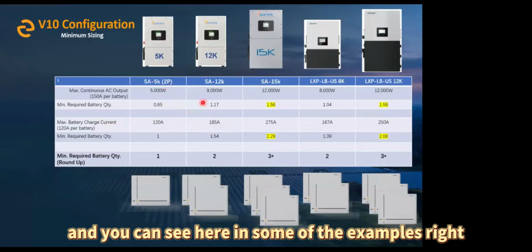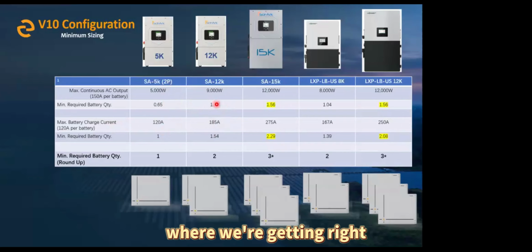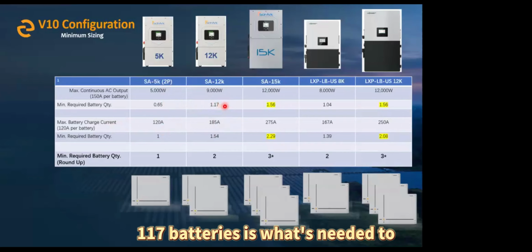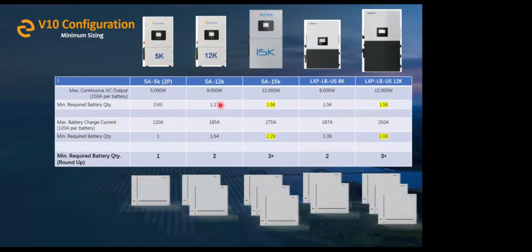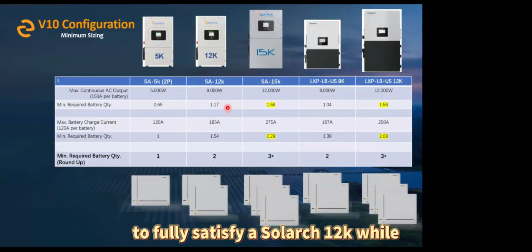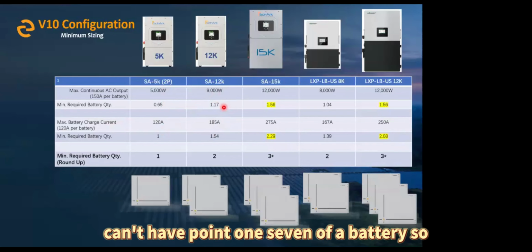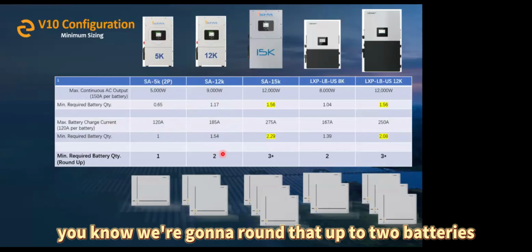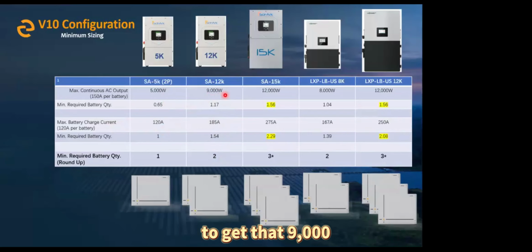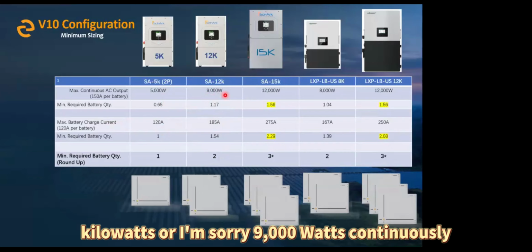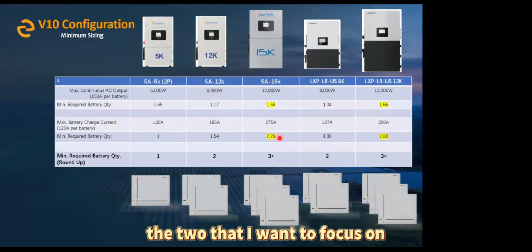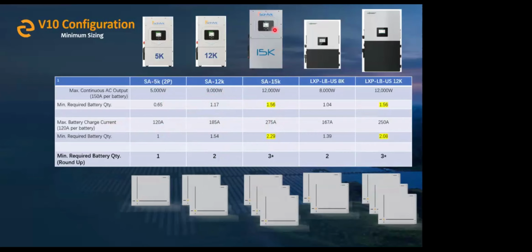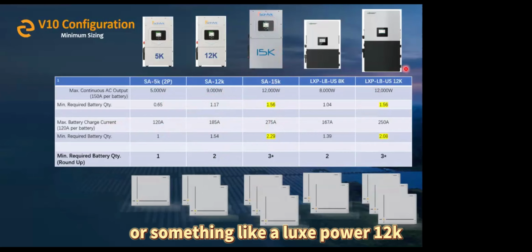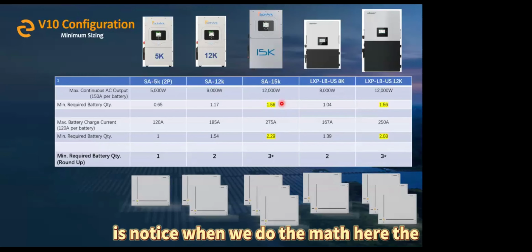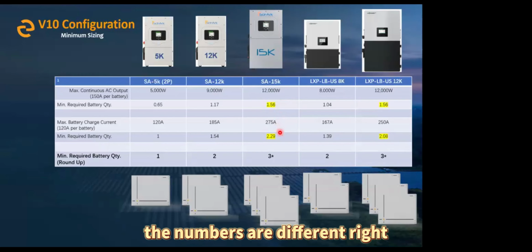And you can see here in some of the examples, we're getting 1.17 batteries is what's needed to fully satisfy a Sol-Ark 12K. Well, can't have 0.17 of a battery, so we're going to round that up to 2 batteries to get that 9,000 watts continuously. The 2 that I want to focus on, in the case of a Sol-Ark 15K or something like a Lux Power 12K - notice when we do the math here, the numbers are different, right?